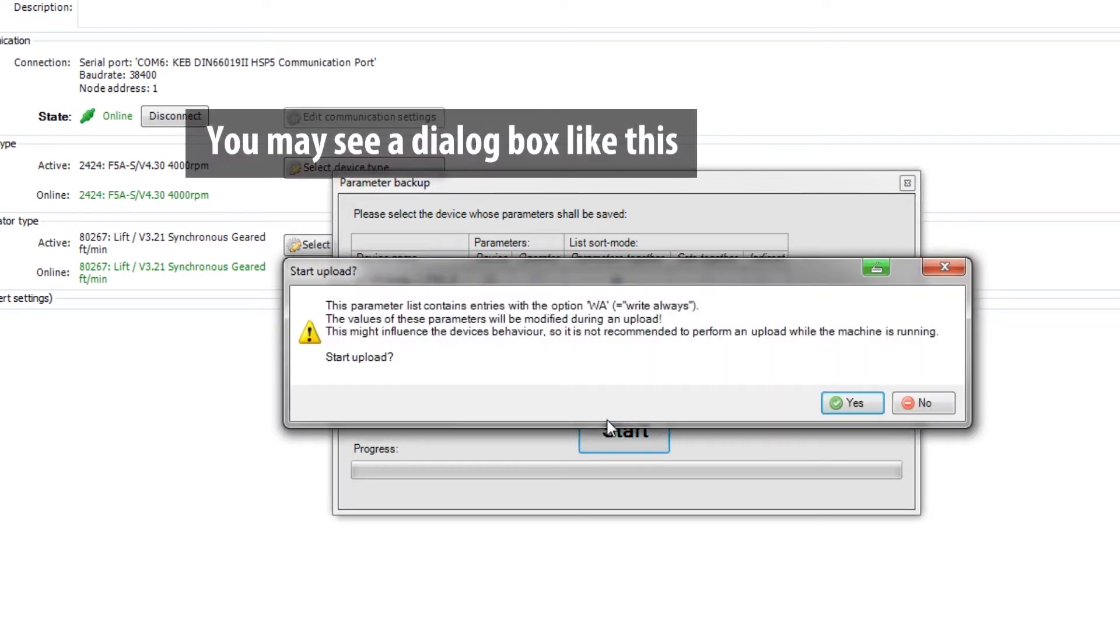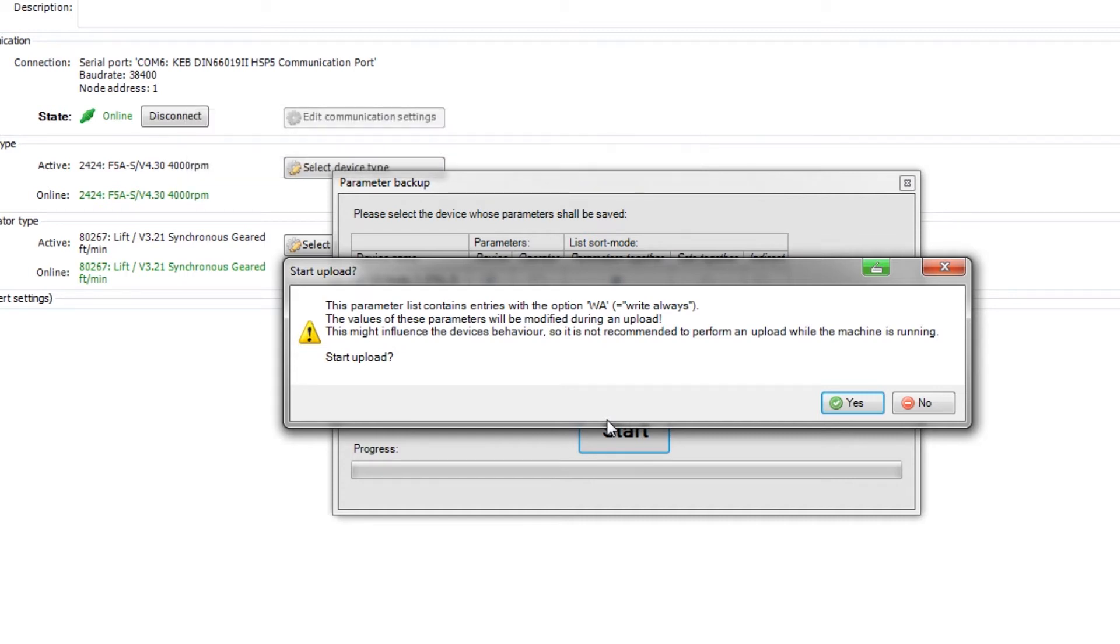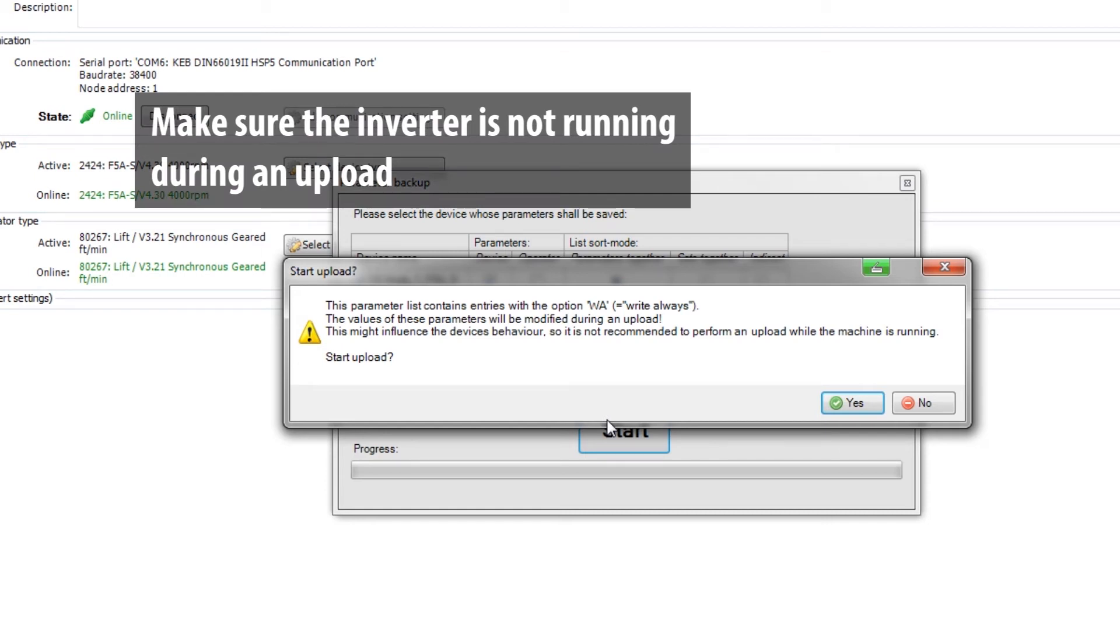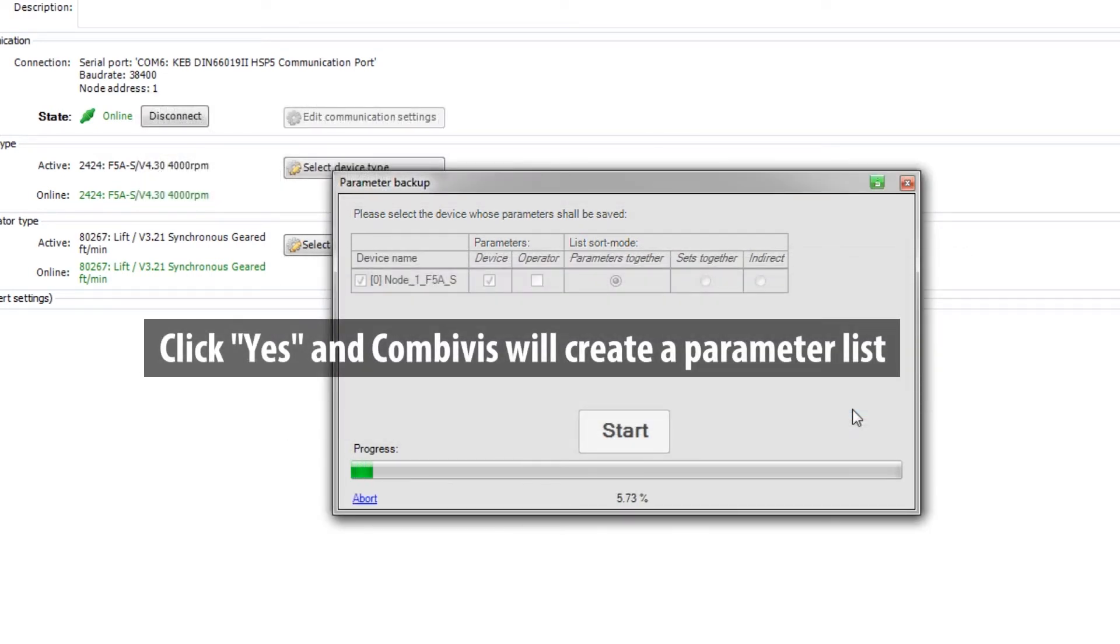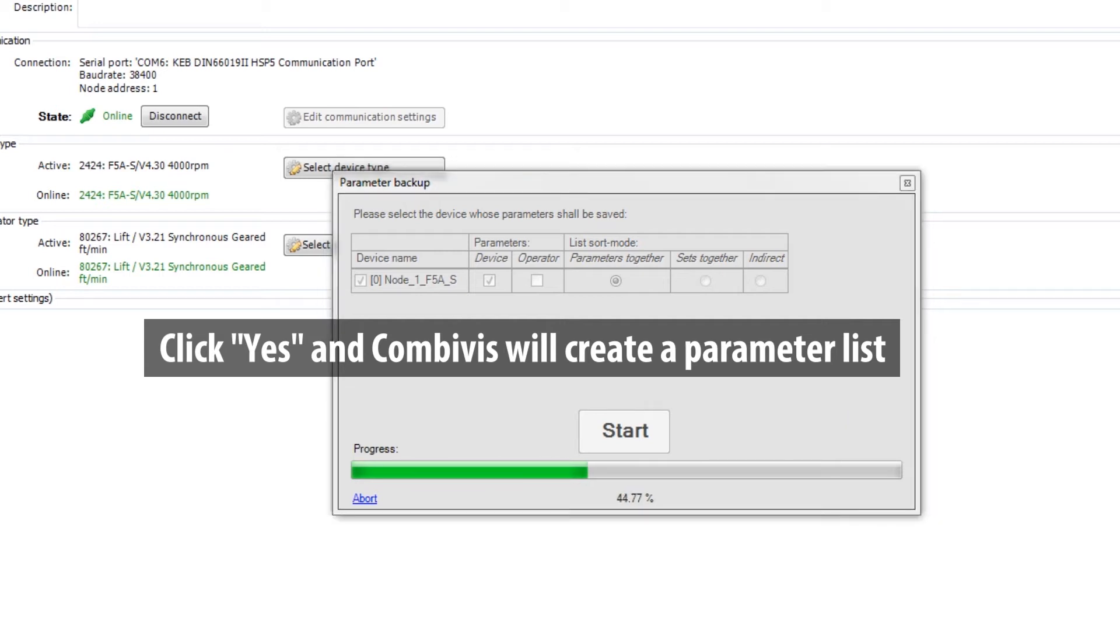CombiVis may create a dialog warning that some parameters are write always. It is best to ensure that the inverter is not running while you are doing a parameter upload, as it may influence the inverter's behavior. Click Yes on the dialog once you are sure that the inverter is not running, and CombiVis will create a parameter list.